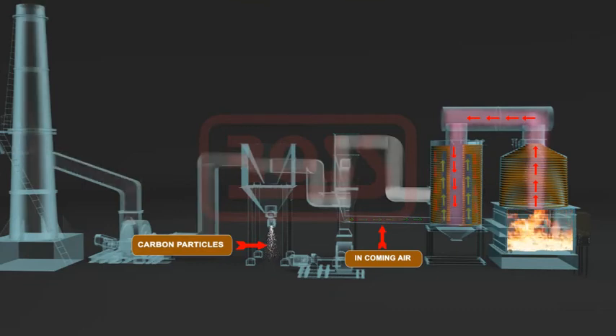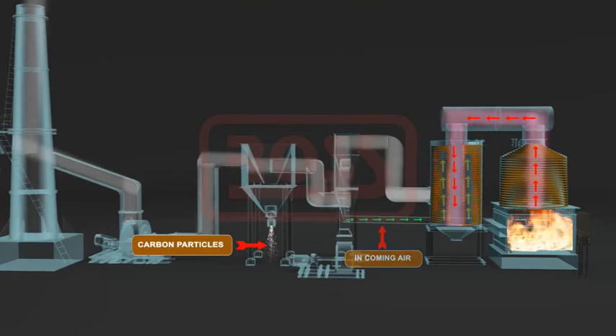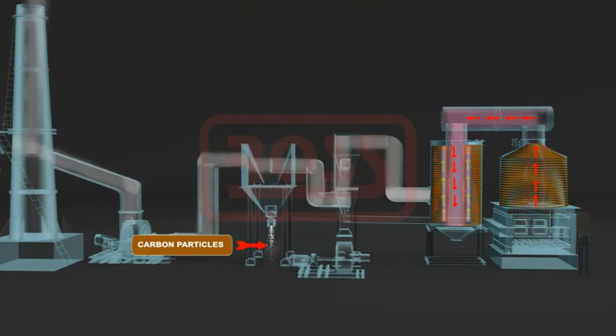Returned thermal oil is passed to deaerator tank to remove any vapor. When thermal oil temperature reaches the set value, ID fan is switched off. The fuel burning rate is suddenly reduced and further rise in thermal oil temperature is thus controlled.